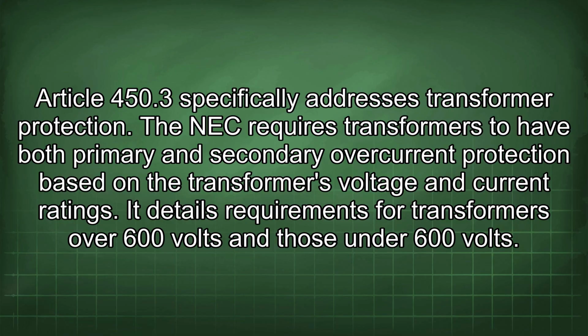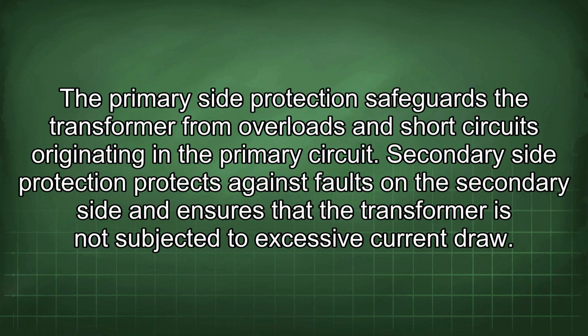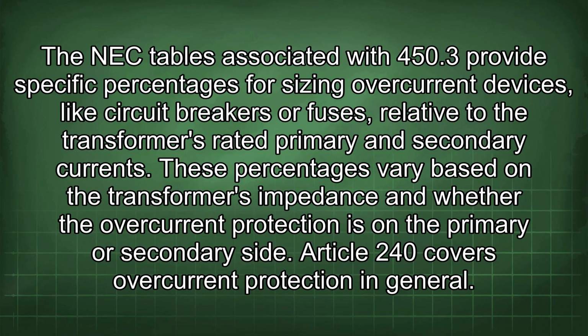The NEC requires transformers to have both primary and secondary overcurrent protection based on the transformer's voltage and current ratings. It details requirements for transformers over 600 volts and those under 600 volts. The primary side protection safeguards the transformer from overloads and short circuits originating in the primary circuit. Secondary side protection protects against faults on the secondary side and ensures that the transformer is not subjected to excessive current draw. The NEC tables associated with 450.3 provide specific percentages for sizing overcurrent devices, like circuit breakers or fuses, relative to the transformer's rated primary and secondary currents. These percentages vary based on the transformer's impedance and whether the overcurrent protection is on the primary or secondary side.